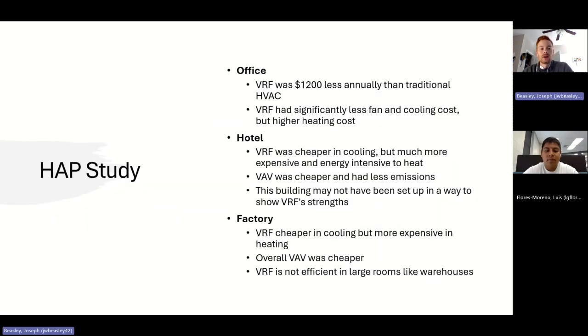We did a HAP study for this report. I put in 3 different buildings. I did a smaller office space, a hotel, and a factory, just to compare variable refrigerant flow to a VAV system, which is a rooftop, traditional HVAC unit. I just used that as a baseline. But anyway, for the office building, VRF was cheaper than the traditional unit because it was much cheaper to cool, and it had a lower fan cost as well. It took less electricity to run the fan, but a much higher heating cost. But overall, it was cheaper to use VRF for the office building.